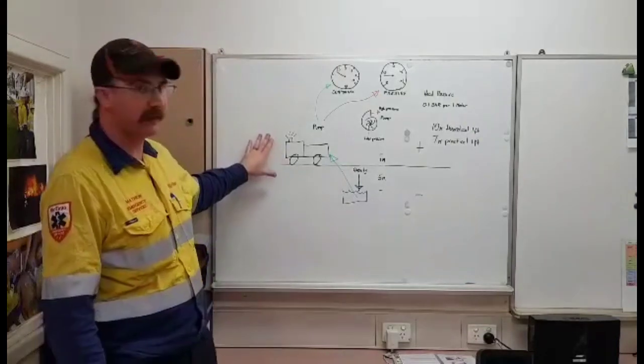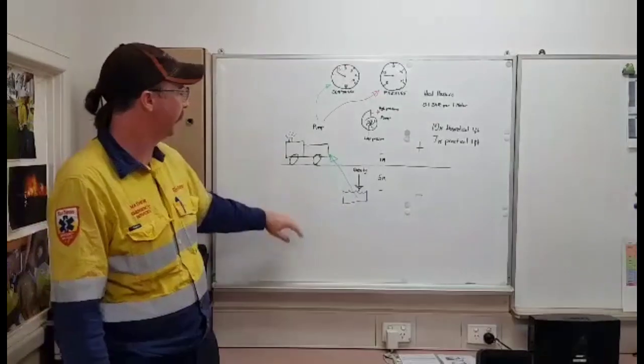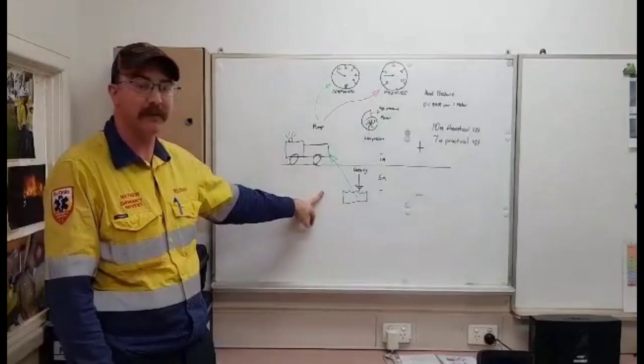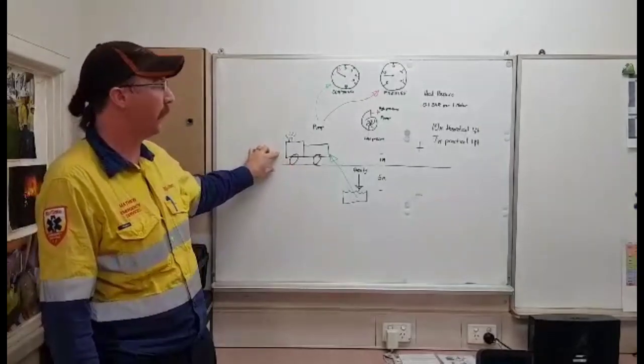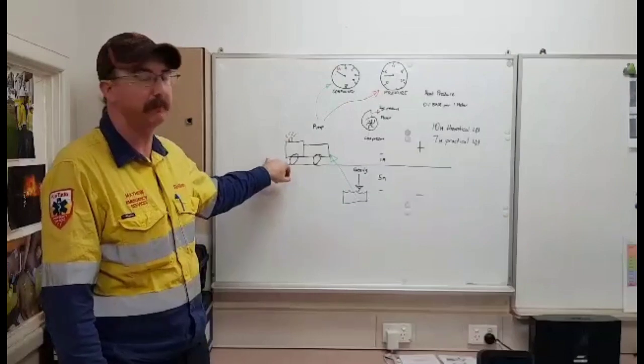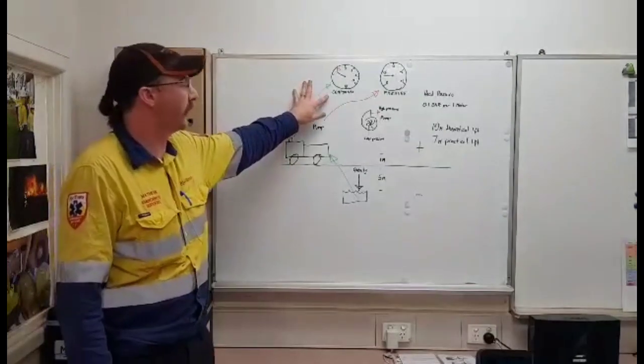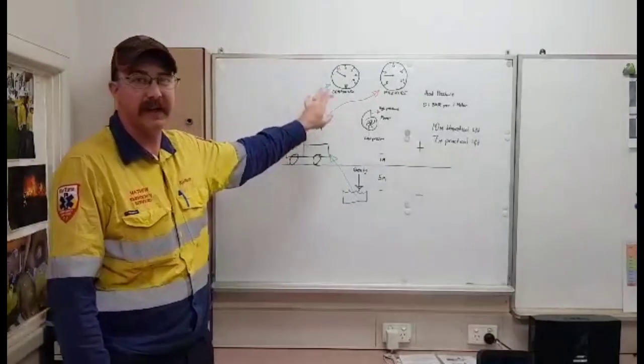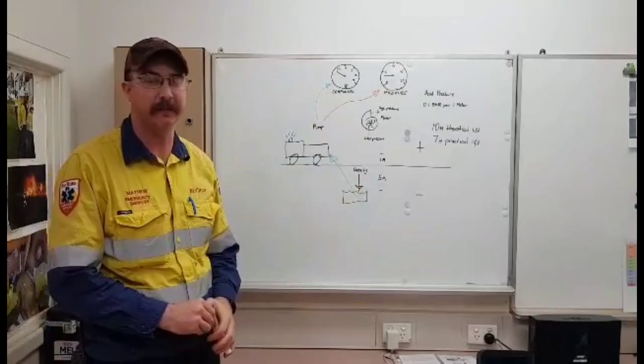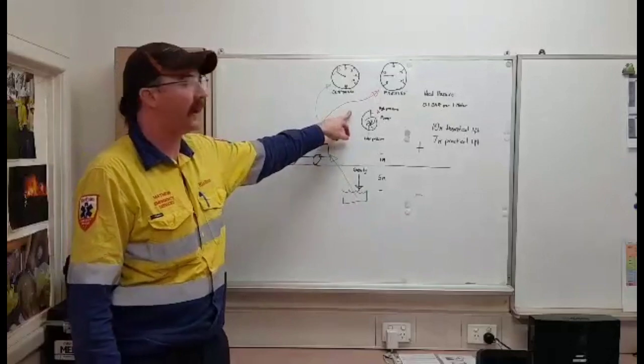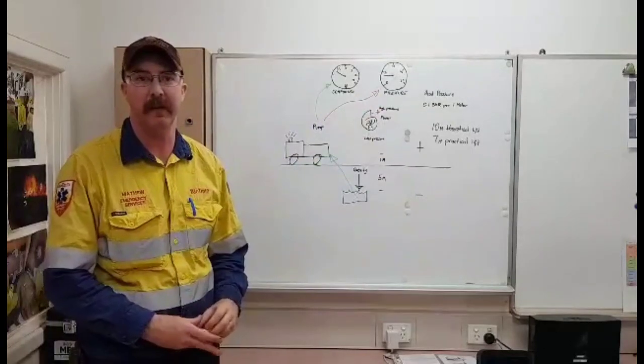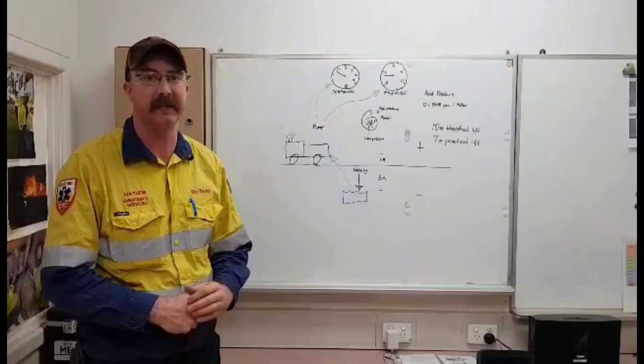So if we look at the context of the drawing here, we have 5 metres between the ground level and the surface of the body of water and we have an additional 1 metre from the ground level to the height of our pump. So this will make our compound pressure gauge read at minus 0.6 bar. Our outlet pressure or the pressure at our deliveries will be determined by what we are trying to achieve downstream.